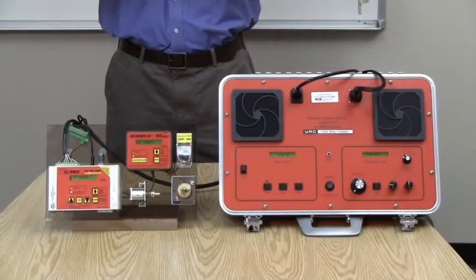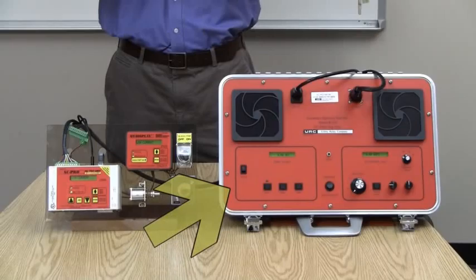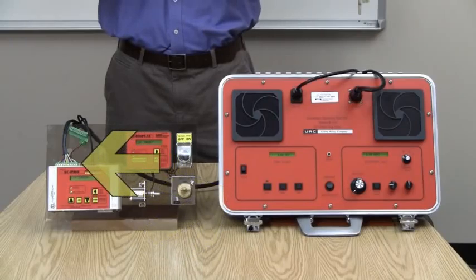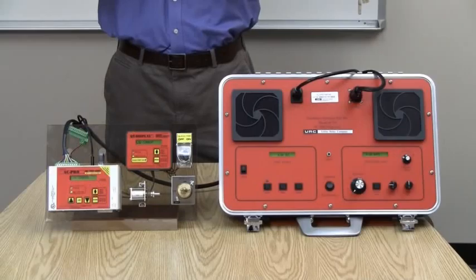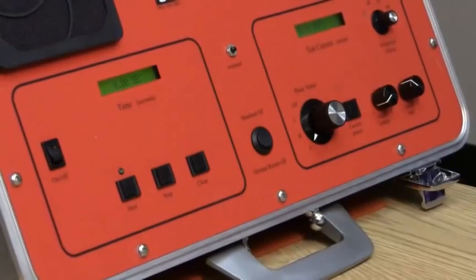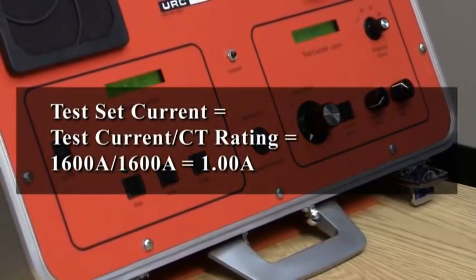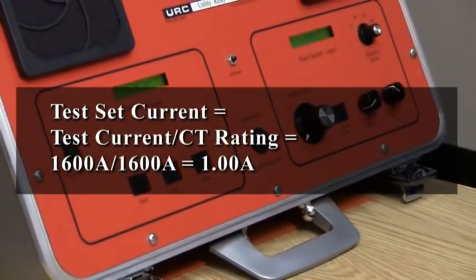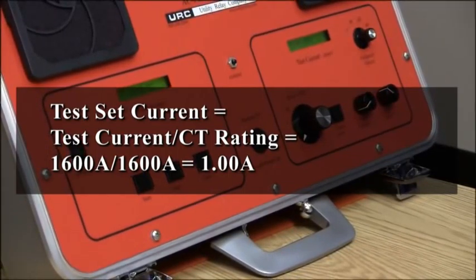The demo setup is connected to our secondary injection test set. The wiring harness from the test set attaches to the top of the AC Pro trip unit and has an extra connector that attaches to the actuator. The first thing we will do with the demo setup is to check the long-time pickup of the AC Pro trip unit. The AC Pro is currently programmed for a 1600 amp CT rating and a long-time pickup of 1600 amps. Therefore, the secondary injection test set should be 1 amp plus or minus 10% at long-time pickup.